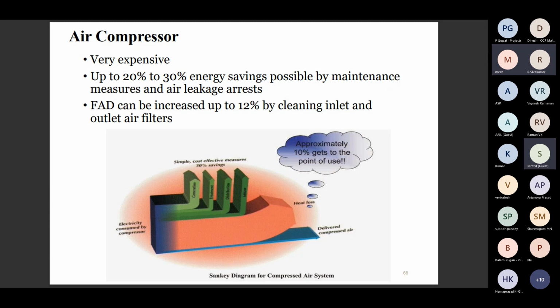For example, we have a 100 HP air compressor, 75 kilowatt, which means we are producing only 15 HP of compressed air. The remaining 85 HP goes for various losses. So the air compressor is a very expensive energy equipment, and there are a lot of potentials for reducing the energy. Up to 20 to 30% energy saving is possible by simple energy saving measures and arresting air leakages at regular intervals. The FAD is nothing but free air delivery. It can be increased up to 12% by regularly cleaning the inlet and outlet air filters.